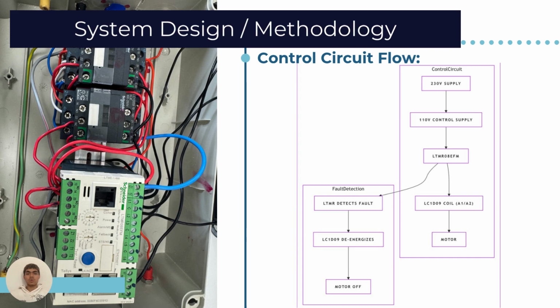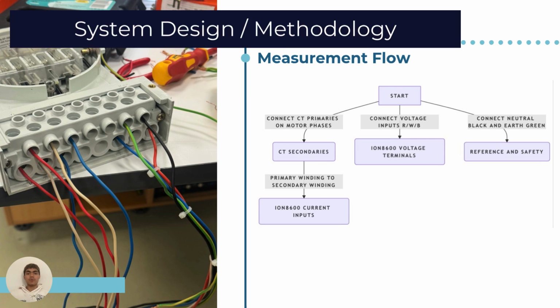Let's jump into the control circuit flow. So the 230 volt supply goes down to 110 volts by the voltage transformer, which feeds the relay, and the relay feeds the contactor during normal condition, and then it goes right up into the motor. While during the fault condition, the relay will decide to trip the circuit and then sends the signal to the contactor, which opens the circuit and turns off the motor. So let's jump into the measurement flow.